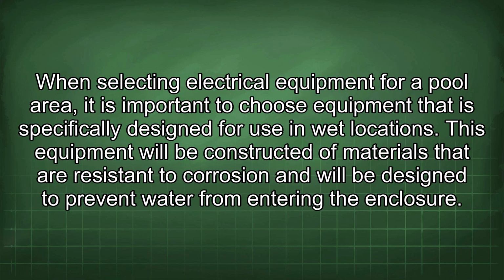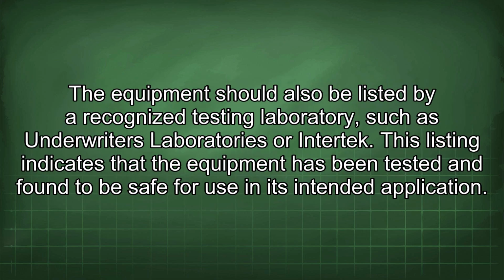When selecting electrical equipment for a pool area, it is important to choose equipment that is specifically designed for use in wet locations. This equipment will be constructed of materials that are resistant to corrosion and will be designed to prevent water from entering the enclosure. The equipment should also be listed by a recognized testing laboratory, such as Underwriters Laboratories or Intertek. This listing indicates that the equipment has been tested and found to be safe for use in its intended application.